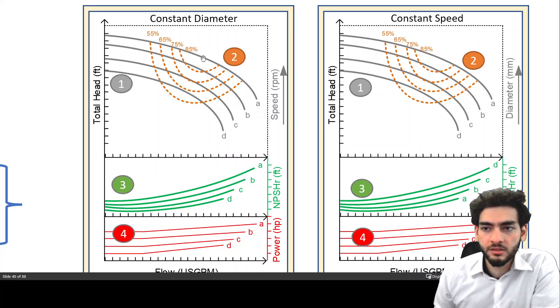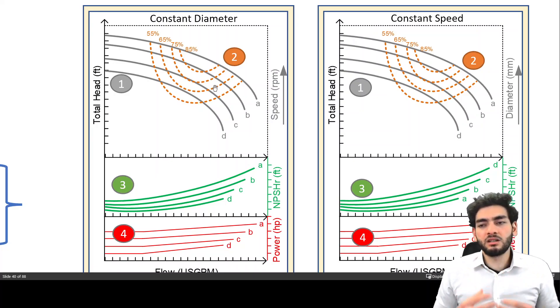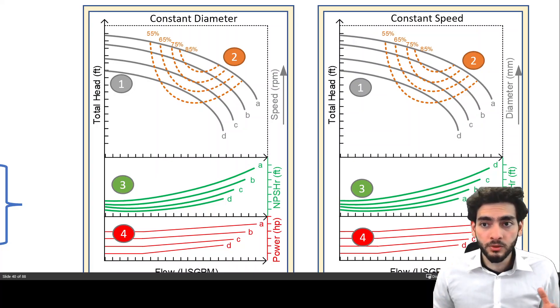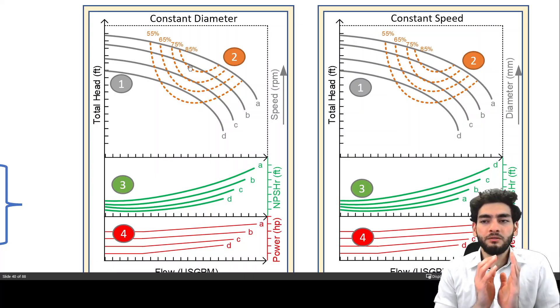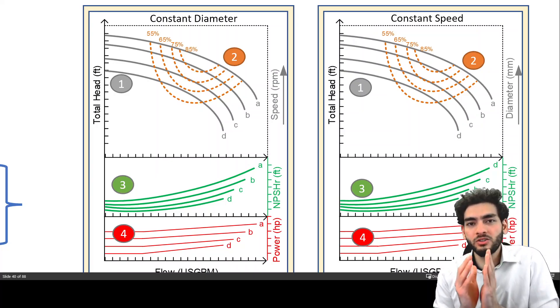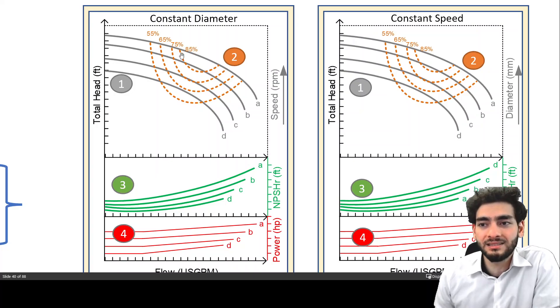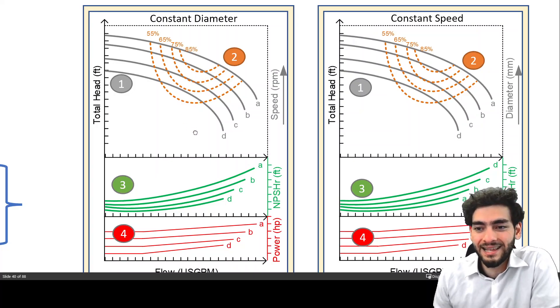And the efficiency curves are these dotted lines. And essentially the point of having these efficiency curves is because you want to operate as close as possible to the highest efficiency possible of the pump. And so the operating point of your pump, you would rather have an operating point of the pump that's as close as possible to a high efficiency or the best operating point. And I will discuss and I'll tell you what best operating point means in a second.